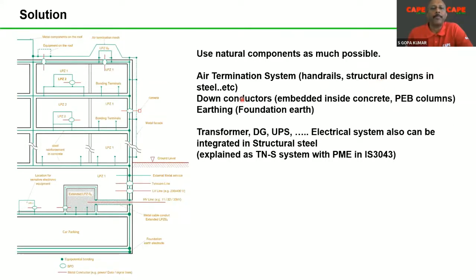This is one. Number two, down conductors. It can be embedded inside concrete. You put an additional conductor, not an MS conductor, and you don't use the rebar, because these two are major challenges, and these recommendations are made in the standard. Not galvanized steel. Better you use copper or stainless steel or copper bonded material. These 3 materials can be used, which do not have any side effects. Then you can also use the PEB columns. Nowadays, a lot of high-rise buildings are with the PEB columns, steel columns, that also can be used.